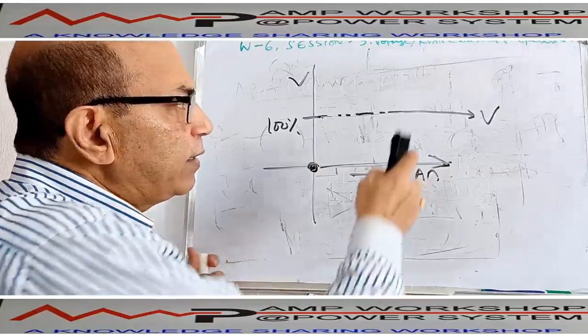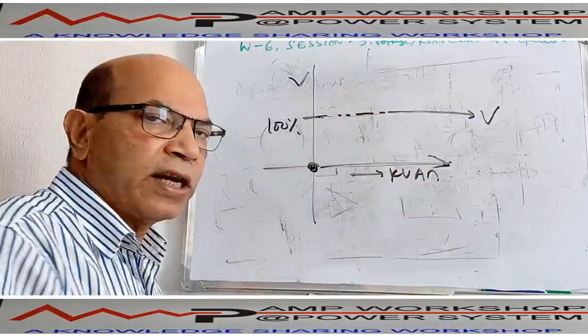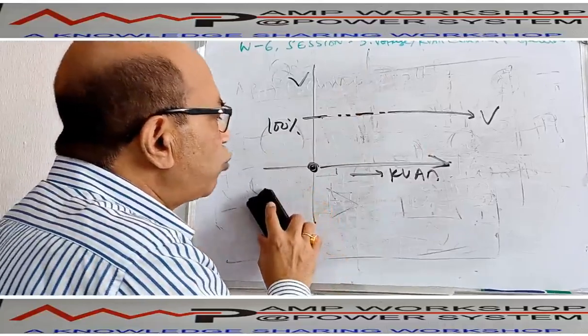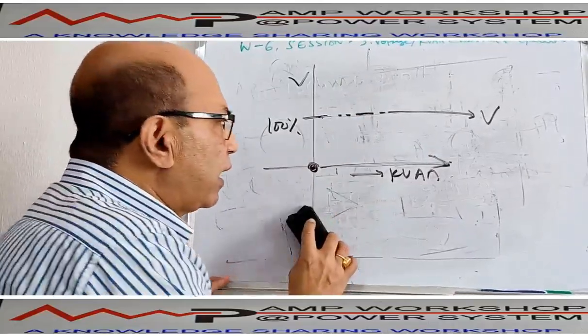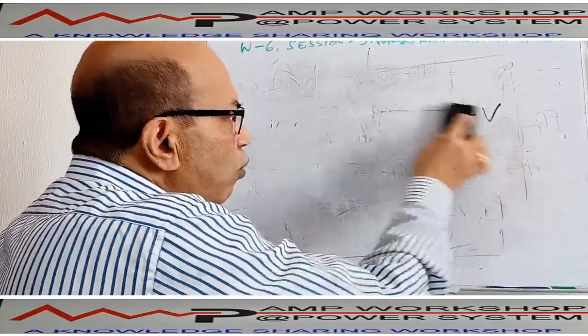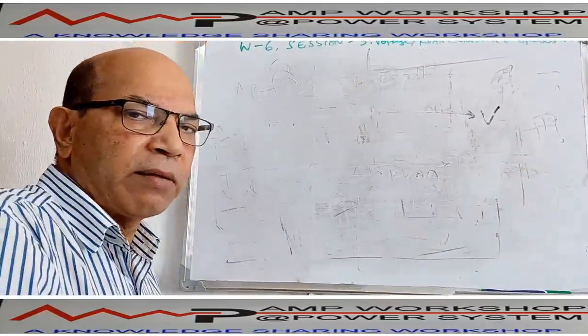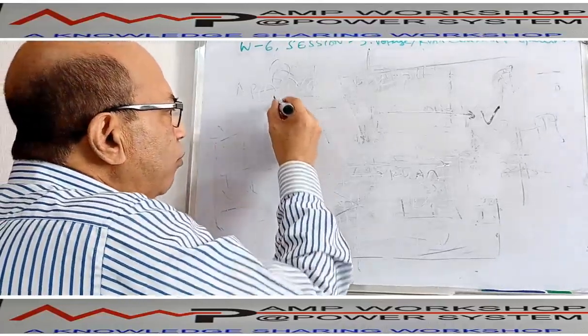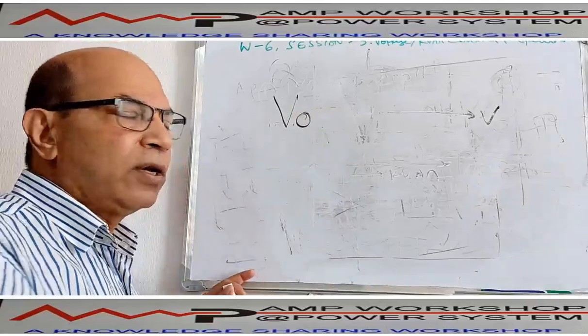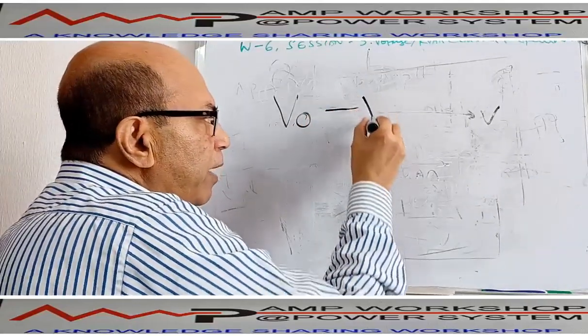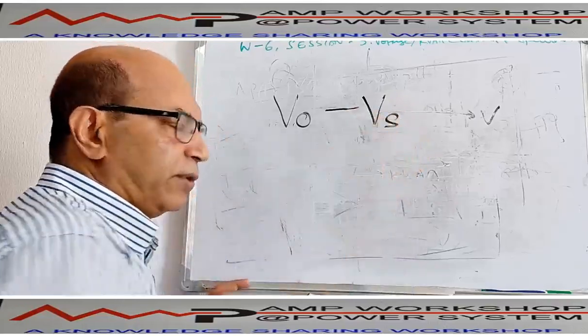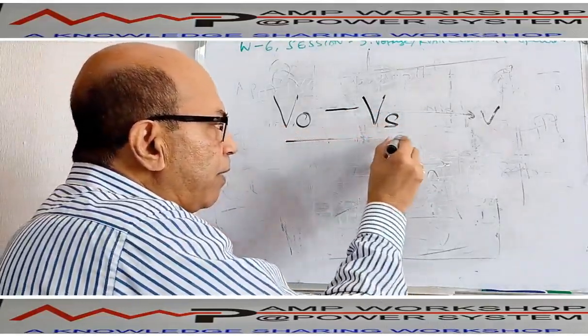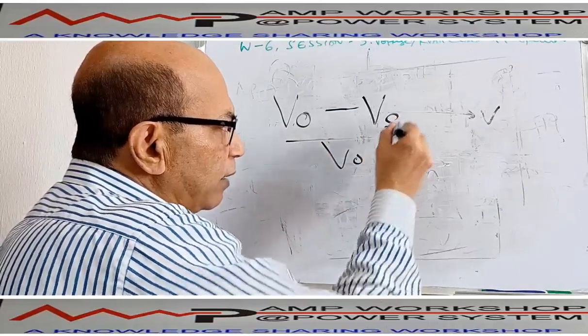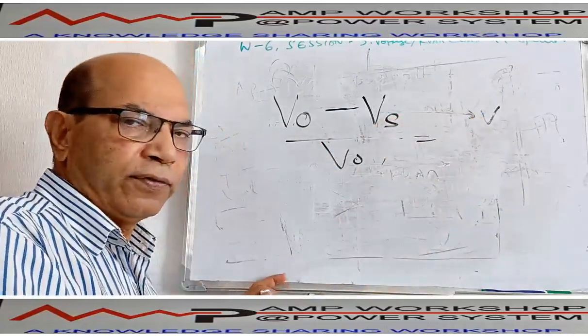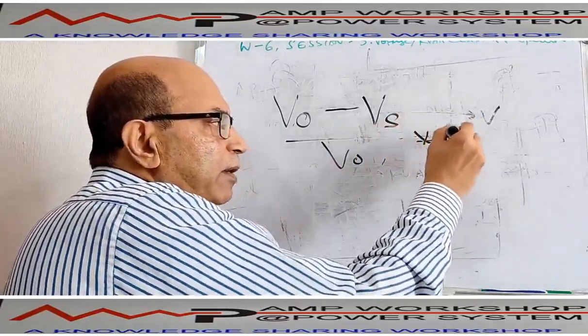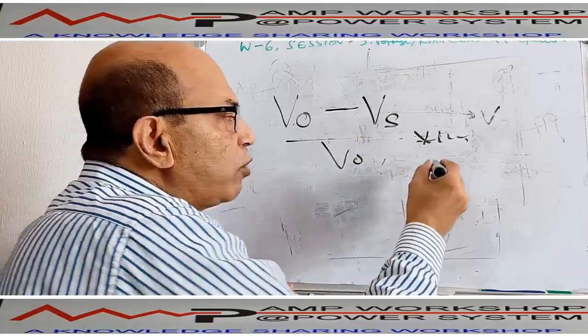But if the voltage is not fixed, and with KVAR loading the voltage drops in proportion, then we call it a droop characteristic, which comes from the same definition. When there is no KVAR on the machine, zero KVAR drawn by the machine, the voltage is the no load voltage, call it V0. When the machine is loaded, there will be a voltage drop, giving say VS. Then the difference of voltage divided by the no load voltage, or you can use the rated voltage, and multiplied by 100, is the percentage voltage drop. This percentage voltage drop we call the droop.